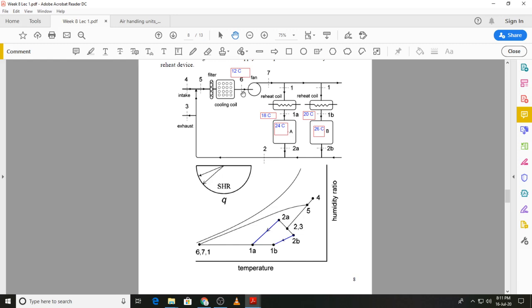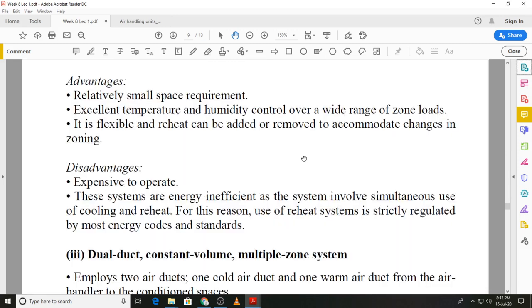The terminal reheat system requires relatively small space, and temperature and humidity control is very good. It is flexible — reheat can be added or removed according to changes in the zone load. However, the prime disadvantage is energy cost: it is expensive to operate and energy inefficient. For this reason, especially with today's emphasis on energy conservation, the use of these systems is quite strictly regulated by most energy codes and standards across the globe.